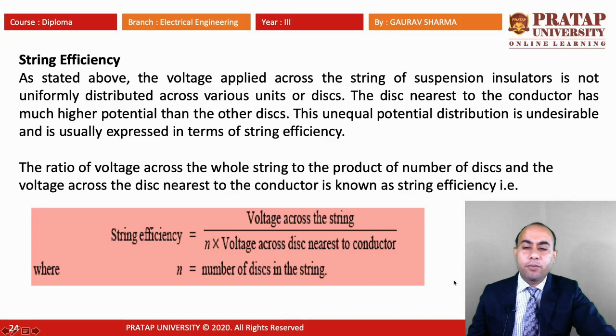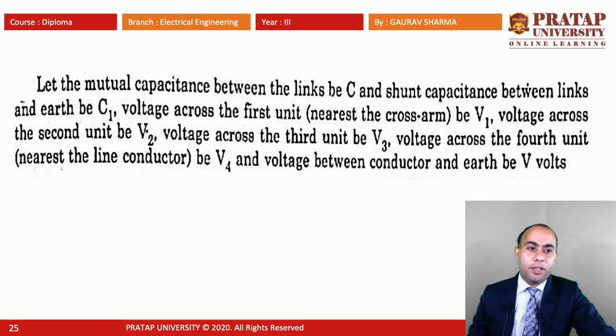Now let the mutual capacitance between the links be capital C and the shunt capacitance between the link and the earth be C1. The voltage across the first unit, which is nearest to the cross arm, is V1, the voltage across the second unit is V2, across the third unit is V3, and across the fourth unit is V4, and the voltage between the conductor and the earth is V. Here we are assuming that we have a 4 unit string insulator. Here is the diagram of the 4 unit string insulator, with C, C1, V1, V2, V3, V4, and the voltage between the conductor and the earth V.